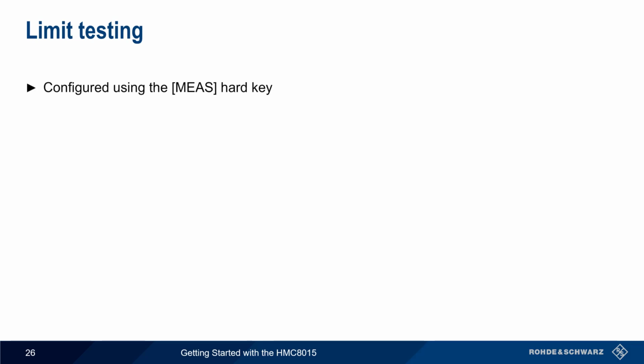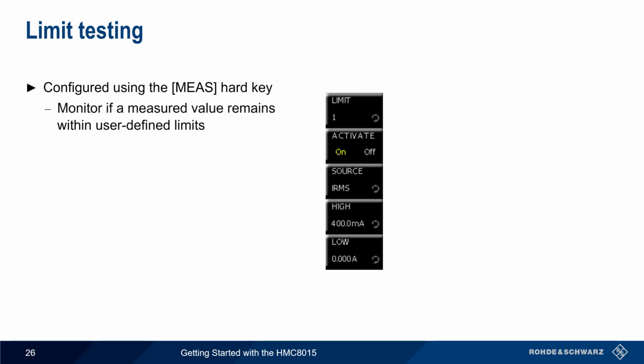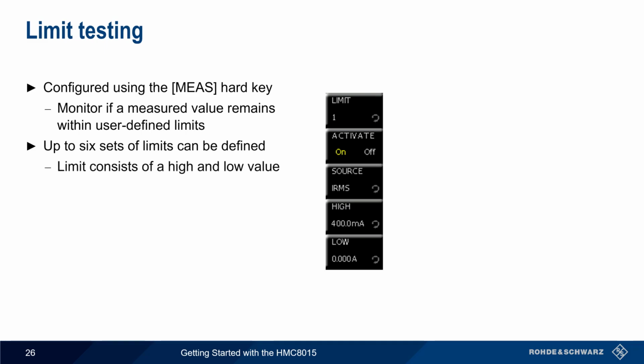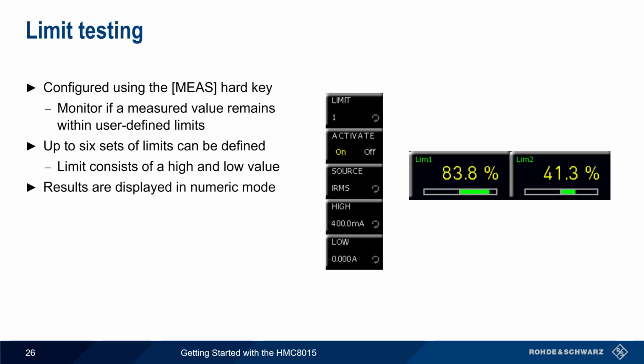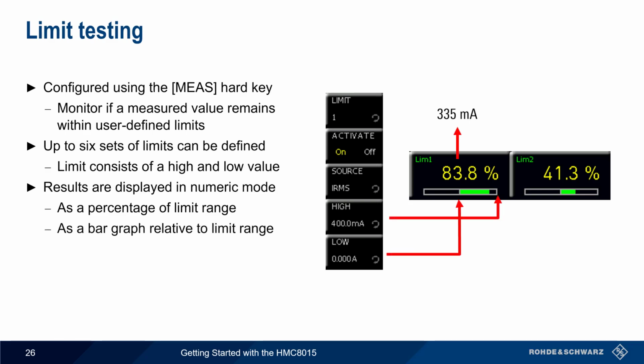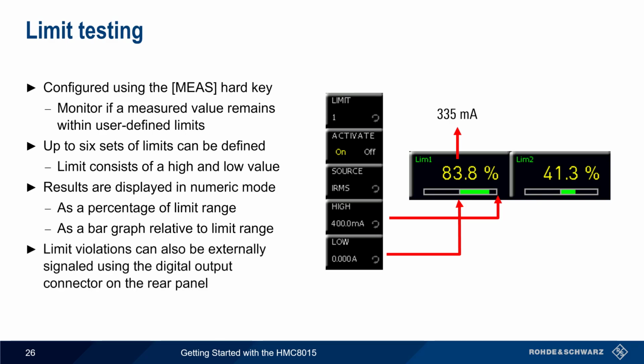Another numeric mode function is limit testing, which is configured via the Measure hard key. Limits monitor whether a measured value, such as current, power factor, etc., stays within user-specified limits. Up to 6 sets of limits can be defined, where each limit has a high and low value for the measured parameter. Limit results are displayed in two ways, both as a percentage of the limit range and as a bar graph relative to that range. For example, the RMS current limits are defined here as 0 to 400 milliamps, so a limit value of 83.8% corresponds to a measured value of 335.2 milliamps. Limit violations can also be externally signaled using the digital output connector on the rear panel.